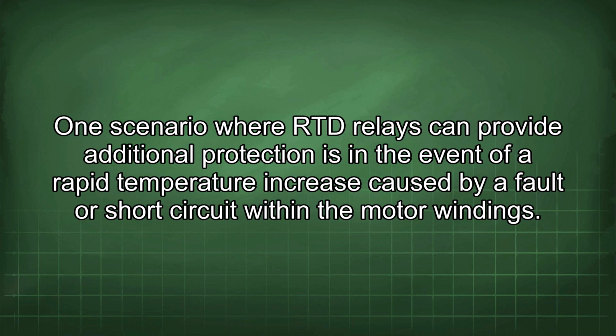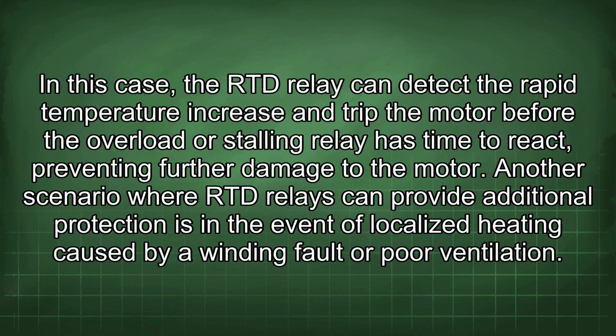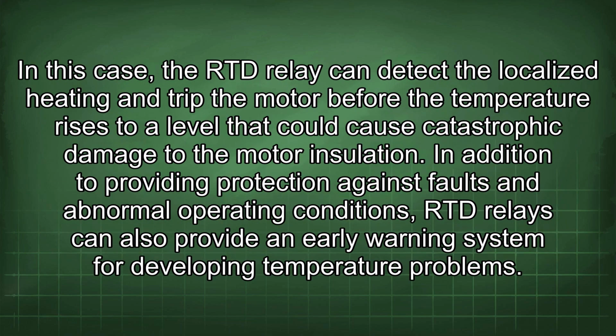One scenario where RTD relays can provide additional protection is in the event of a rapid temperature increase caused by a fault or short circuit within the motor windings. In this case, the RTD relay can detect the rapid temperature increase and trip the motor before the overload or stalling relay has time to react, preventing further damage to the motor. Another scenario where RTD relays can provide additional protection is in the event of localized heating caused by a winding fault or poor ventilation. In this case, the RTD relay can detect the localized heating and trip the motor before the temperature rises to a level that could cause catastrophic damage to the motor insulation.